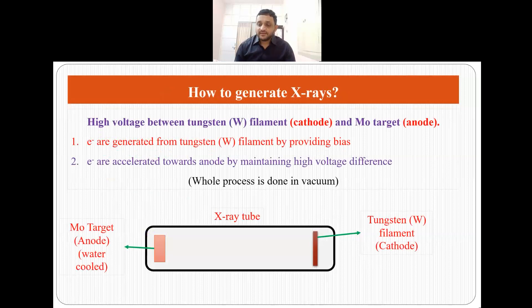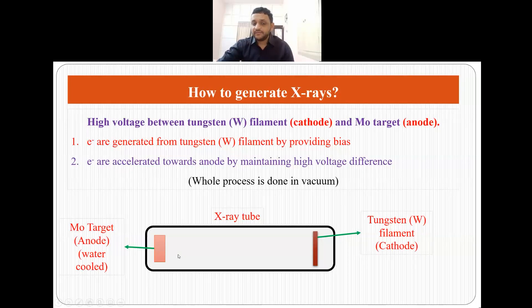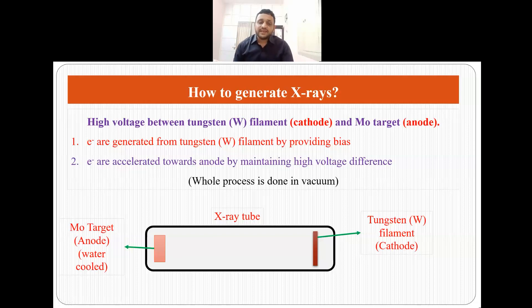To generate x-rays, we have a tungsten filament which is the cathode, and electrons are generated by providing bias. We maintain a high voltage difference between the cathode and the anode, which is our molybdenum target. Since there is a high voltage difference, the electrons accelerate towards the anode, strike the molybdenum target, and generate heat and x-rays. It is very essential that the molybdenum target be water cooled so that it does not degrade in the process.